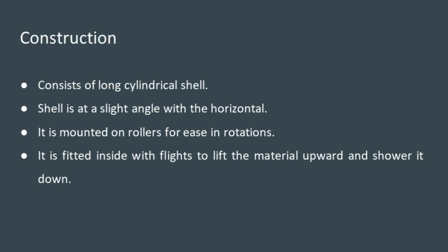having a diameter of about 1 meter to 3 meter and length 3 meter to 30 meter. The shell is set at a slight angle with its horizontal axis inclined towards the outlet so that the material fed is consequently advanced through the dryer from one end to the other end under gravity.